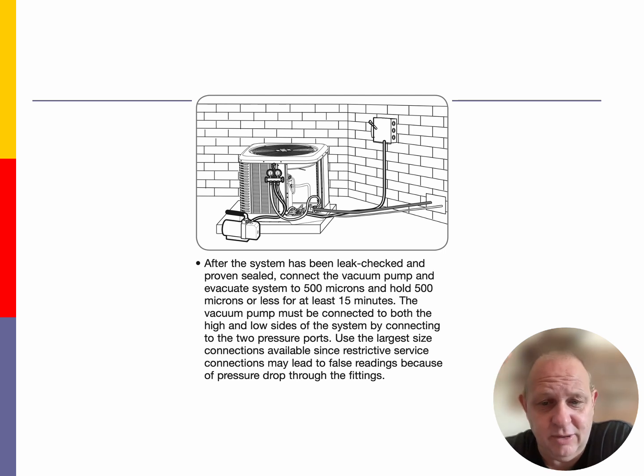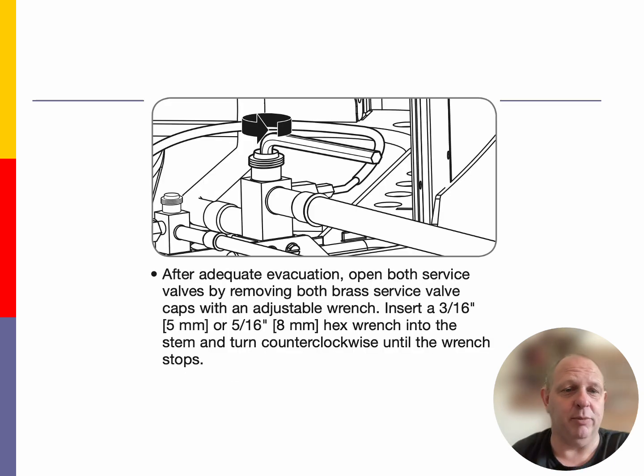If it continues to rise and rise and rise, we have a leak. But if it comes up and it settles out at a certain micron level, then we're good to go into our next step. And the next step would be to open up the valves on that system. So once we have adequately vacuumed the system and pressure tested the system, we can open up these valves on the outdoor unit. And what this will do is release the refrigerant that the manufacturer has put on the inside of the unit and let it go into the system so that we're ready for this system to actually operate.